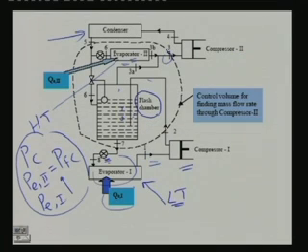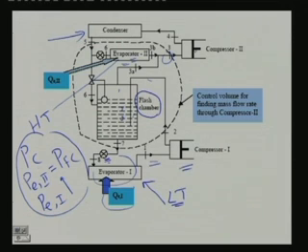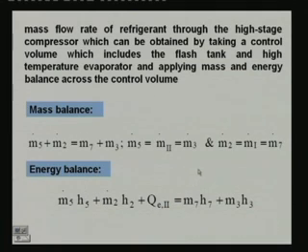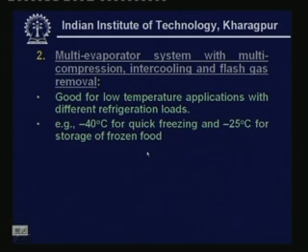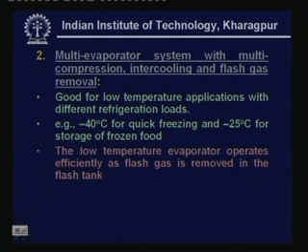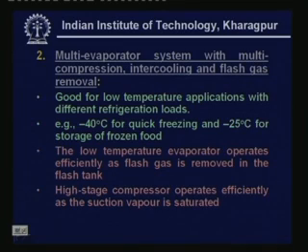The advantages of the multi-evaporator multi-compression system are: it is good for low-temperature applications with different refrigeration loads — for example, minus 40°C for quick freezing and minus 25°C for frozen food storage in a food processing plant. The low-temperature evaporator operates efficiently because flash gas is removed in the flash tank, and the high-stage compressor operates efficiently because the suction vapor is saturated.